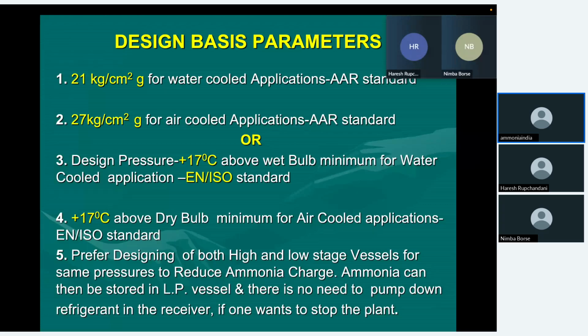I always prefer in my projects designing both high side and low side pressure vessels for the same pressure, so that anytime you close the plant, you don't have to pump down the liquid from the low pressure side into the high side ammonia receiver, and thereby you reduce the size of the ammonia receiver, and you don't have to rush every time to pump down the system.